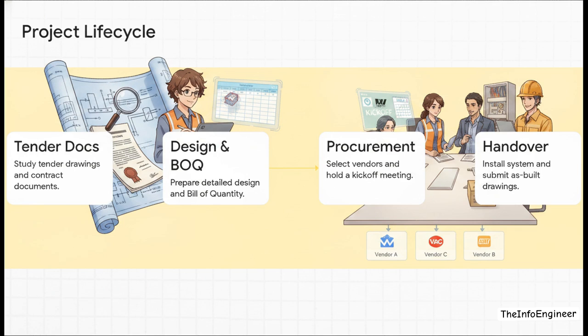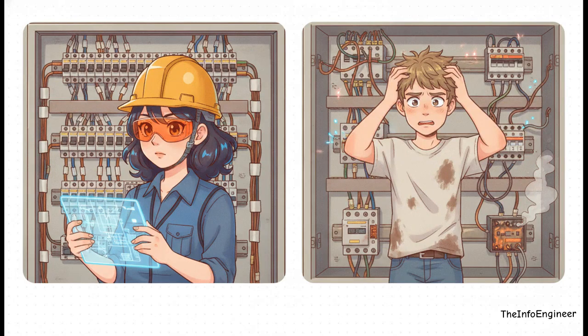And finally, after the installation is done, you enter the strict handover phase, passing over operations manuals and, crucially, your as-built drawings. And that brings us to a really critical distinction. We have to separate the pros from the amateurs. Professional execution is driven by rigorous documentation, detailed single-line diagrams, quality plans, neatly labeled wire diagrams inside your distribution boards. If your site is characterized by chaotic panels and zero as-built drawings, you aren't delivering an engineering solution. Honestly, you're just engaged in a really expensive, dangerous hobby.